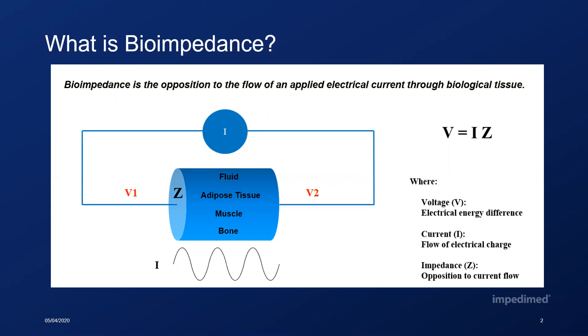As the current flows it loses energy, and the resulting energy loss across the body caused by the material or tissue is measured by the difference in voltage between a second set of sensing electrodes — so V1 minus V2. Ohm's law relates the voltage to the current and impedance, and therefore measurement of the voltage difference and current flow can be used to determine the resulting bioimpedance.